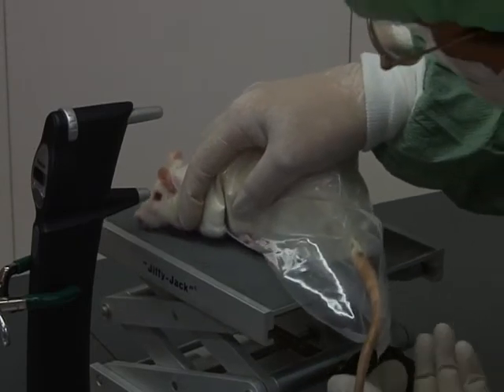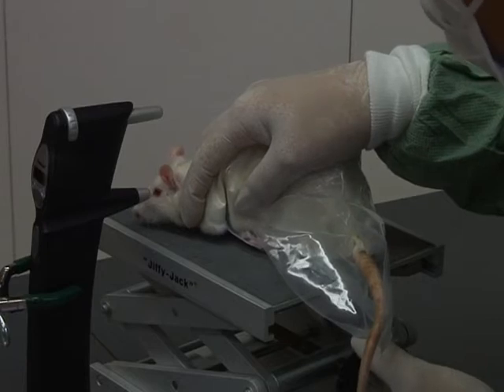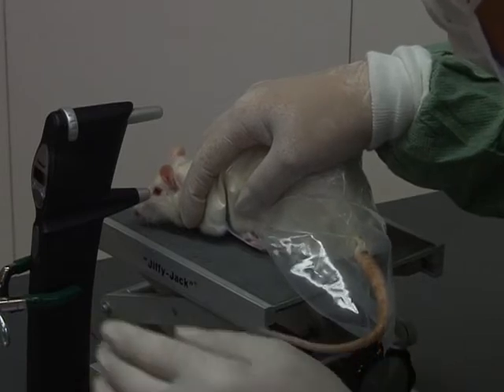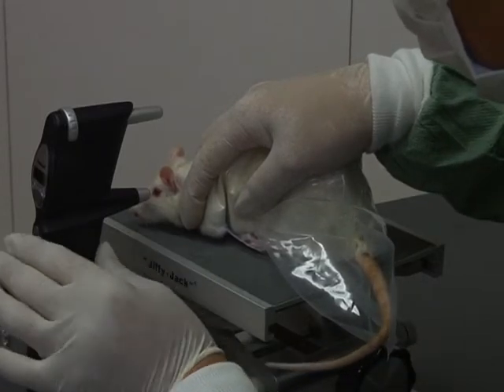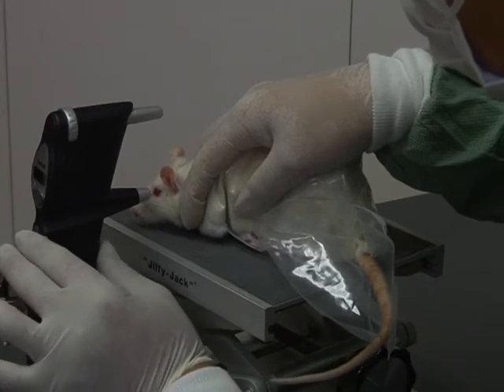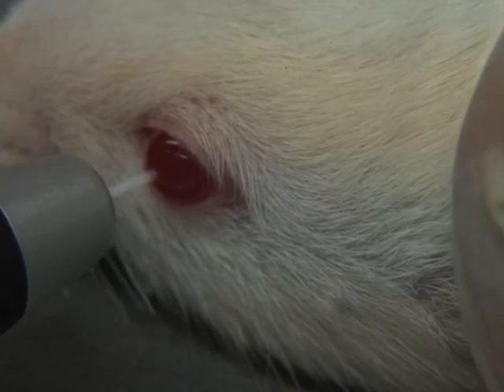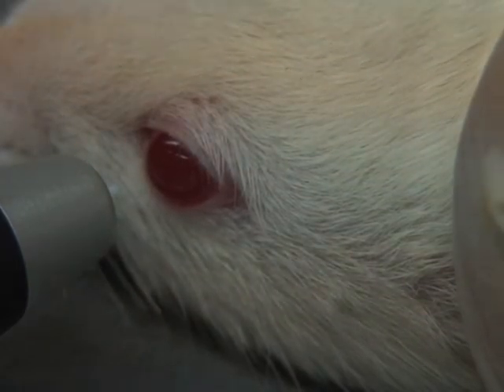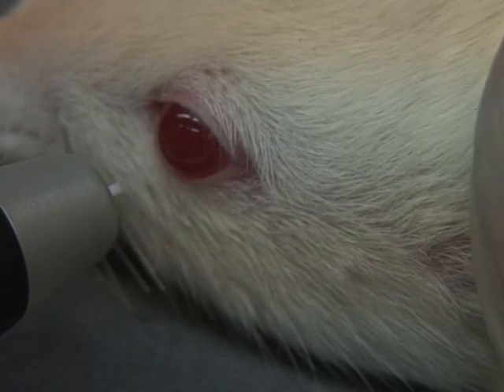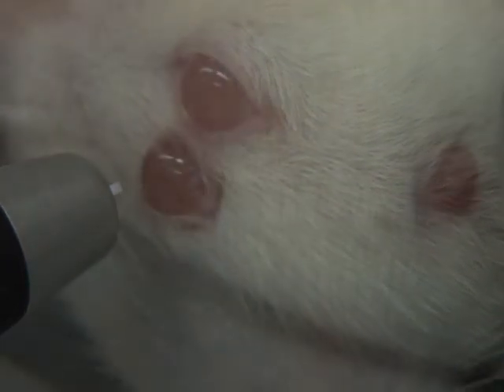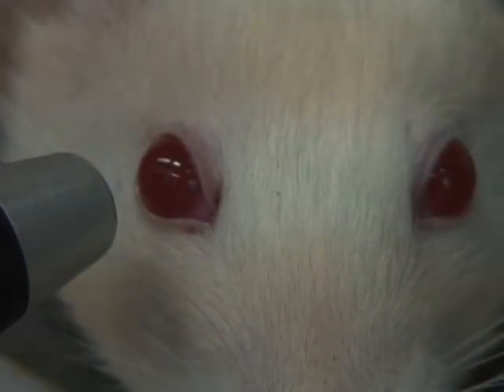The rat is placed on the platform with its head gently secured between two fingers. Bring the rat eye near to the probe tip. Adjust the height of the platform and change the rat body posture until the probe tip can hit the very center of the cornea and is aligned with the optical axis of the eye. IOP measurements are then performed using the TonoLab.